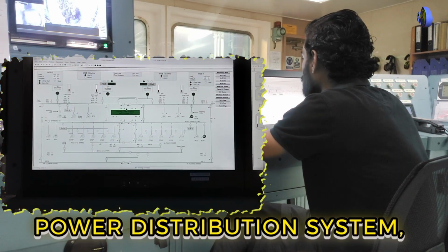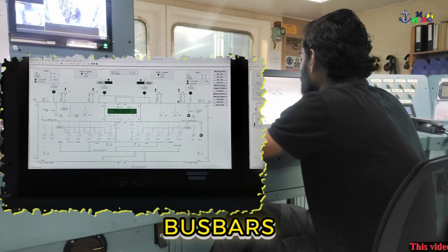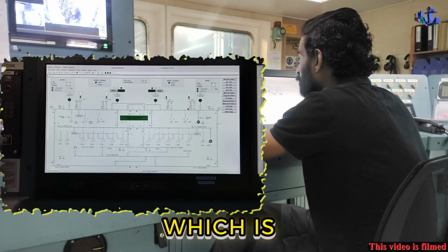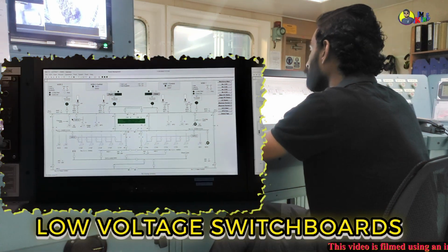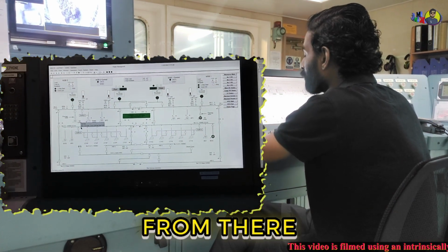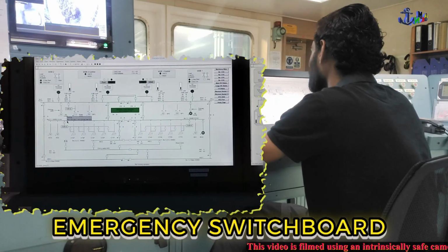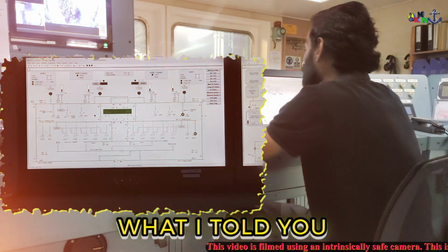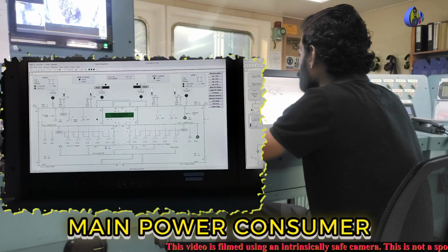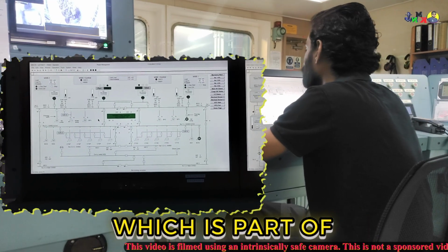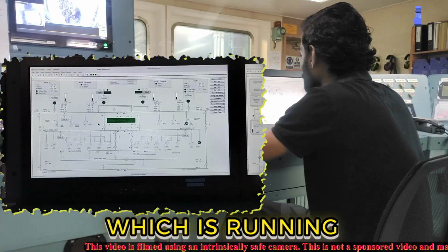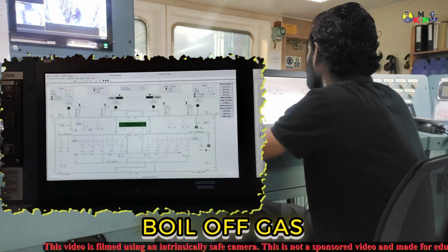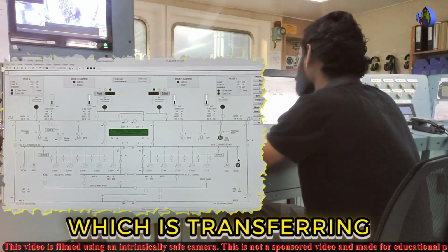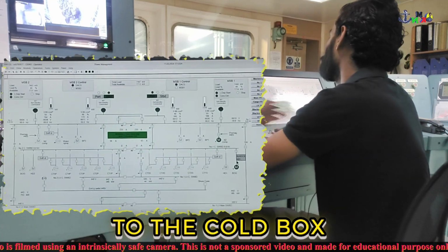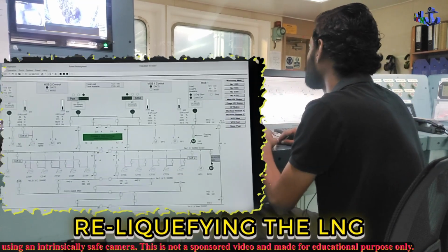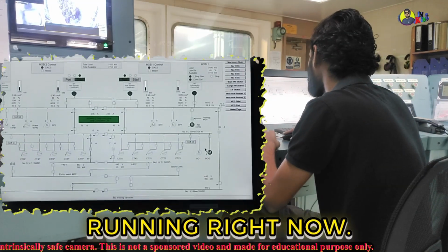In this power distribution system, we have 2 main bus bars at high voltage, 6.6 kV, which is divided to low voltage switchboards number 1 and number 2, and from there it goes to the cargo switchboard, emergency switchboard, and other areas. As I mentioned, the main power consumers are our nitrogen compander, part of the re-liquefaction plant, which is running right now, and the boil off gas compressor, which transfers boil off gas from the cargo tank to the cold box, re-liquefying the LNG and putting it back into the tank, also running right now.